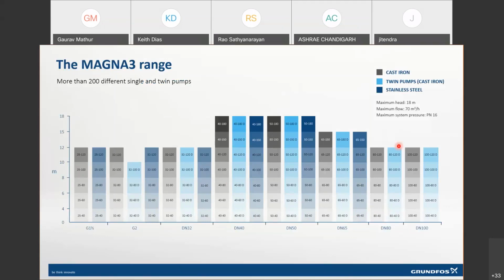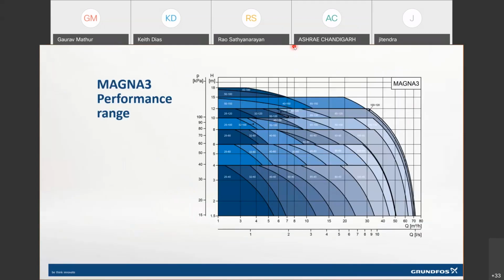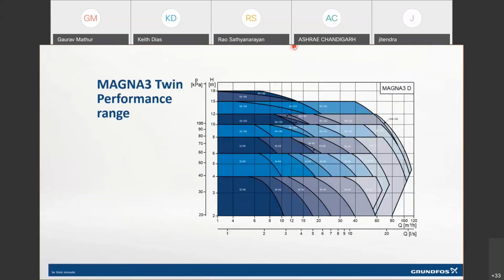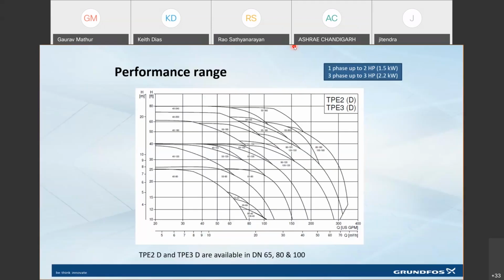We have the range of Magna 3, which covers from 70 meter cube per hour flow up to 18 meters of head, which is the maximum. And this covers mostly a mid-sized commercial building with this flow rate. But if your flow rates are bigger, then you can either go for a twin head system, or you can go for a range of pumps, which is our TPE2 and TPE3 range of pumps.